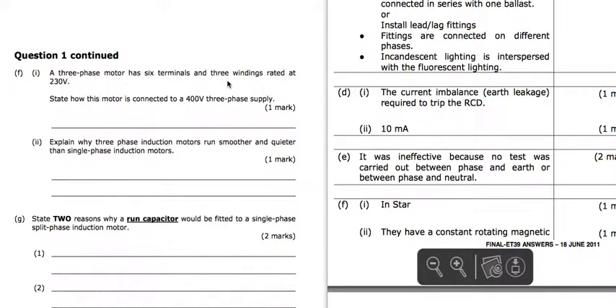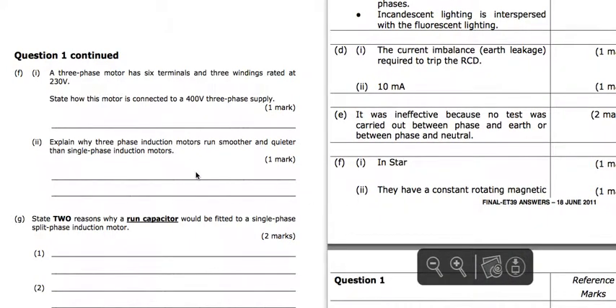3-phase motor, 6 terminals and 3 windings, rated at 230 volts. How are we going to connect this to a 400 volt supply? Well, as soon as we see 230, we know it has to be in star, because across the star winding there's going to be 230 volts.